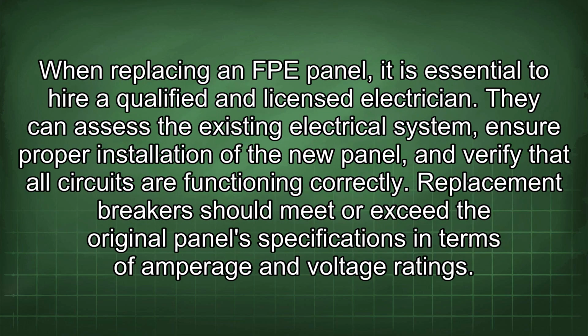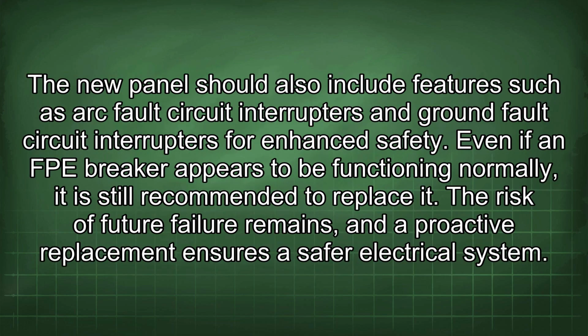When replacing an FPE panel, it is essential to hire a qualified and licensed electrician. They can assess the existing electrical system, ensure proper installation of the new panel, and verify that all circuits are functioning correctly. Replacement breakers should meet or exceed the original panel specifications in terms of amperage and voltage ratings. The new panel should also include features such as arc fault circuit interrupters and ground fault circuit interrupters for enhanced safety. Even if an FPE breaker appears to be functioning normally, it is still recommended to replace it.